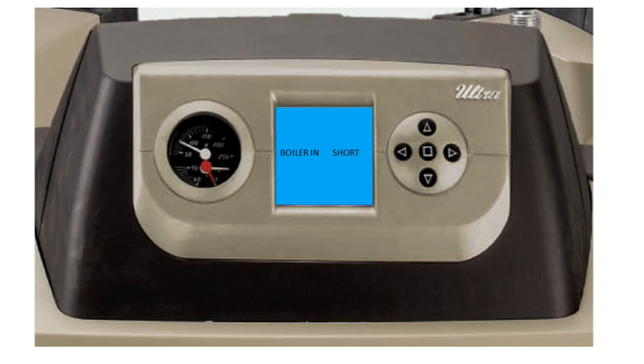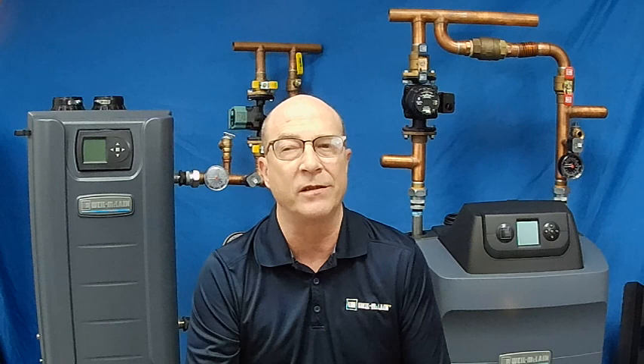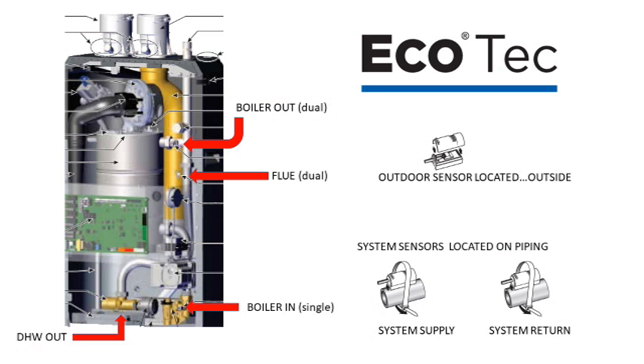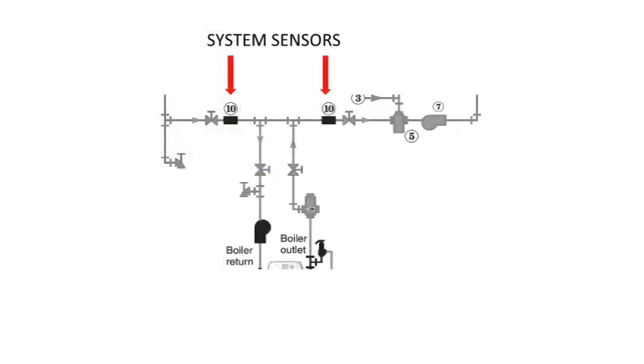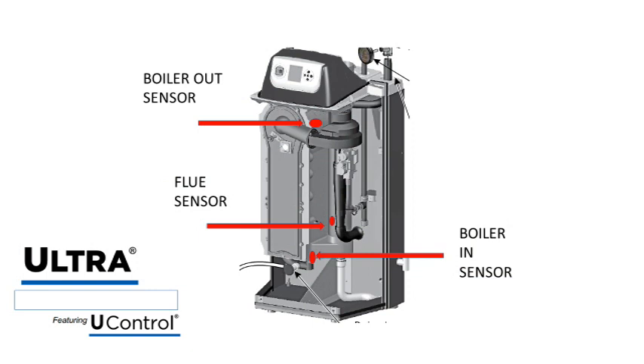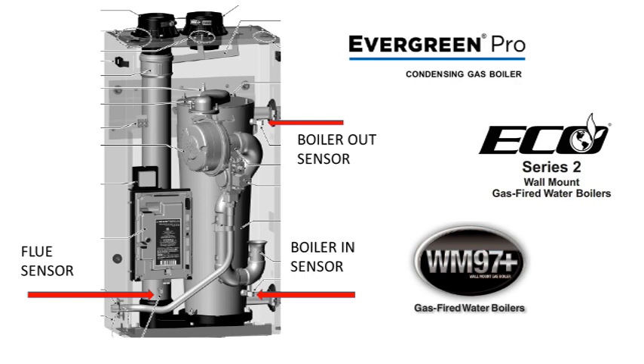There really isn't much to these sensor errors when it comes to determining which sensor is causing the issue. The tricky part can be finding exactly where that sensor is located. Here are a few diagrams of our most common sensor locations. On our EcoTec boiler, we can see the boiler out sensor, the flue sensor, boiler in sensor, and DHW sensor when used. Along with those, we have the outdoor sensor and the system sensors. The system sensors are located on the pipes, usually within three feet of the bypass connection. The outdoor sensor will be outside. Sensor locations for our Ultra Boiler are shown here, and Evergreen, Eco, and WM97 are shown here.